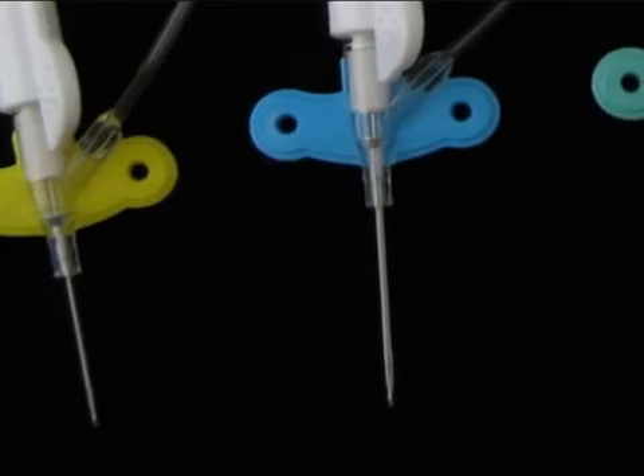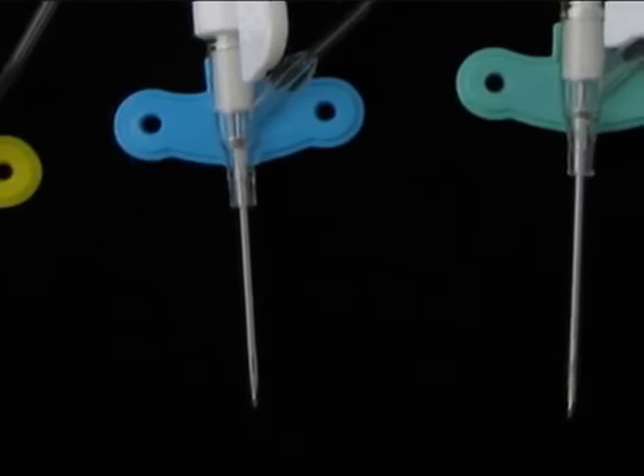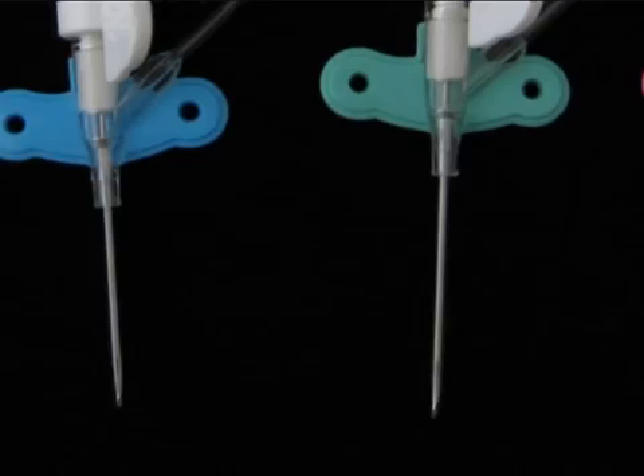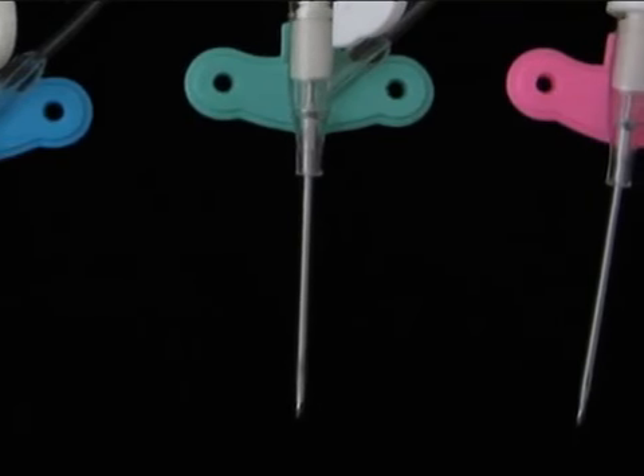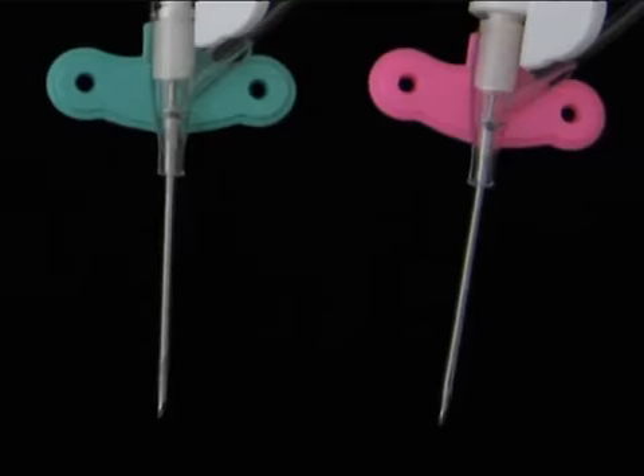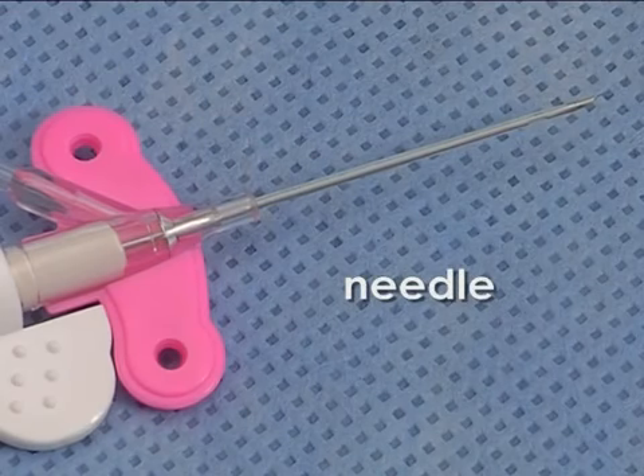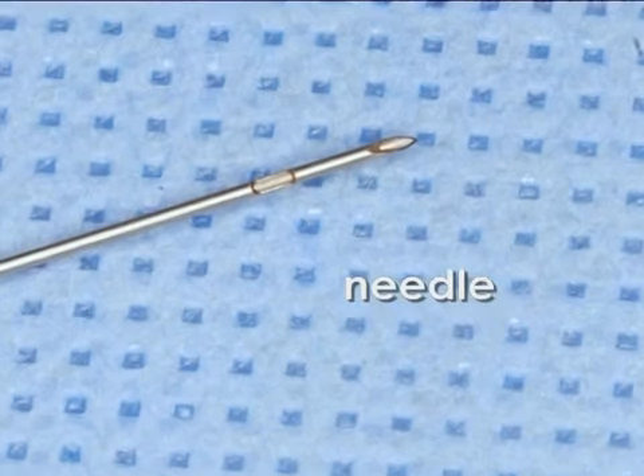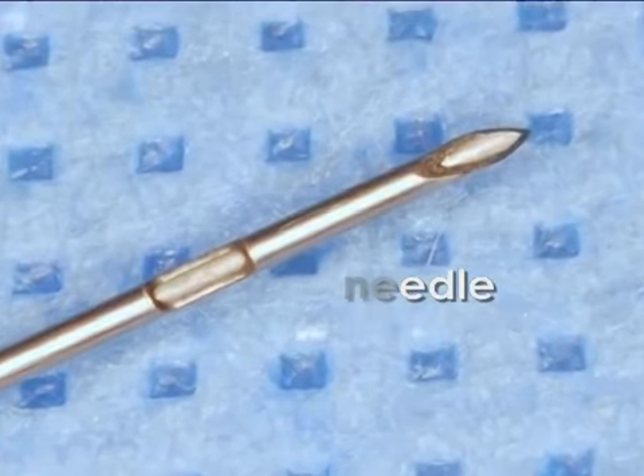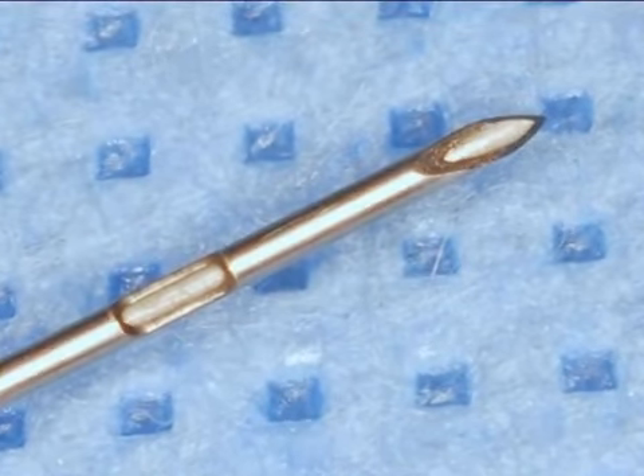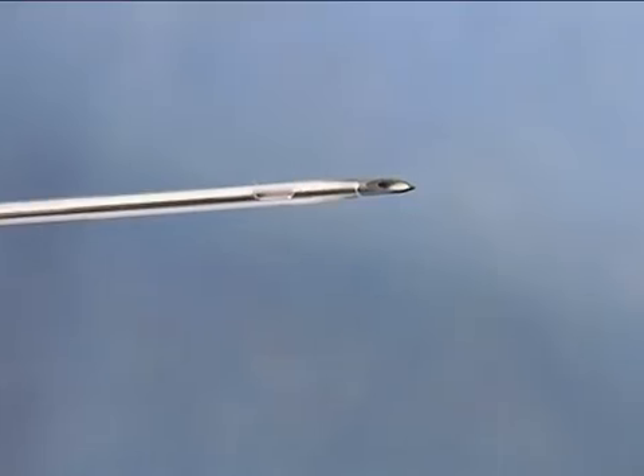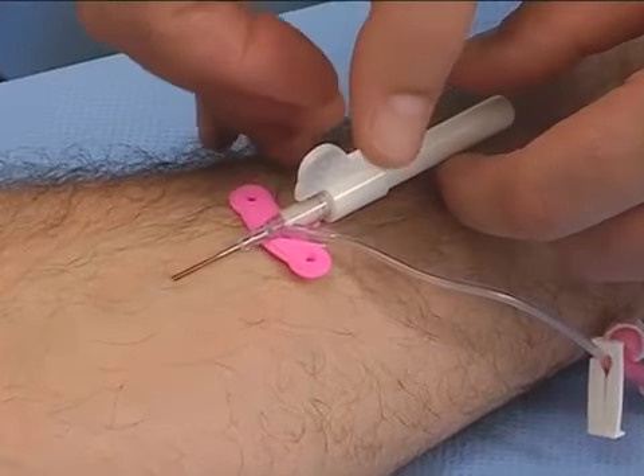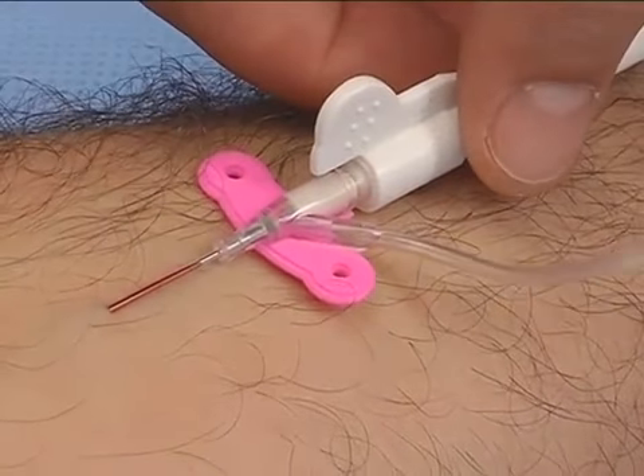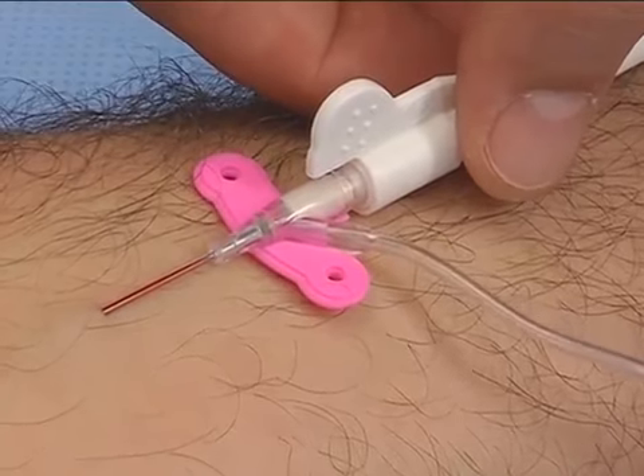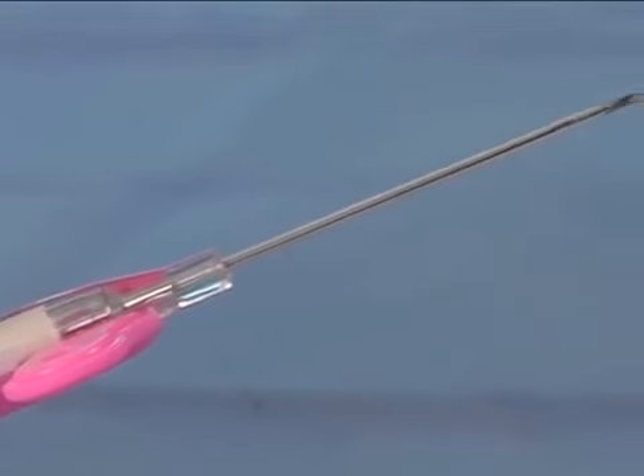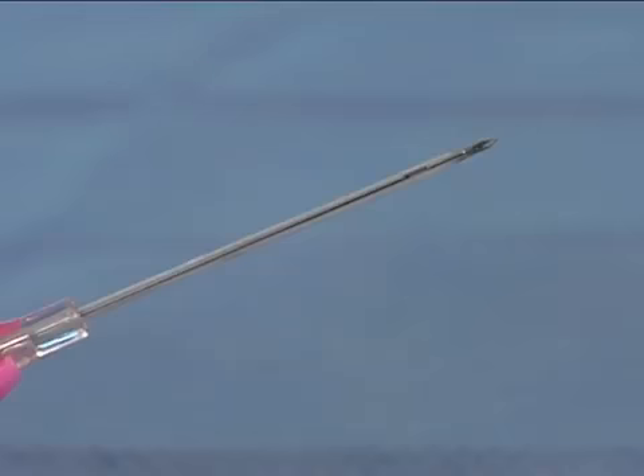The cannula length is slightly greater than standard, variable from 19 to 30 millimeters according to the gauge needed to reduce accidental displacement. The needle produced in Japan is an atraumatic triple sharpened one and is furnished with a lateral window near the tip. This window allows immediate visualization of blood returning along the catheter, thus avoiding side-to-side perforation of the vein, significantly reducing the risk of hematoma, vein rupture, and/or difficult vein acquisition.